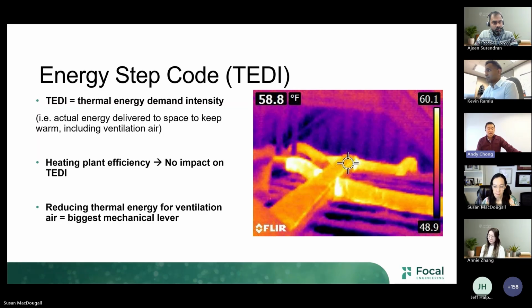It feels a little silly when we're throwing the best and most expensive HRVs at the residential areas, and then we've just been blind to a big source of energy loss, a big penalty on TEDI, in the common areas, the lobbies, the garbage rooms. There are ways we can inject air, positively pressurize the corridor, but it can migrate to another part of the building that needs to be exhausted anyway. Can we draw that out from the garbage chute? Can we draw that out from the waste room? Can we let it trickle down a main circulation stair and grab it out of another area of the building that needed to be exhausted continuously anyway?